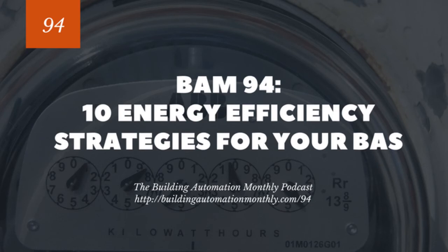Well, by factoring in enthalpy rather than just looking at purely outdoor air, and this is more applicable in very humid states or Midwestern states, and I'm talking about the United States here. I'm not an expert around the rest of the countries in the world, but you could probably make some assumptions. Essentially, you're looking at the amount of moisture that is in the air, and based on that, you're making a decision of how to control your economizer. Now, this is a little more difficult, and enthalpy sensors can definitely be problematic, but it does provide you an opportunity, especially in situations where things are really humid, to control the amount of BTUs of energy you're introducing into your system.